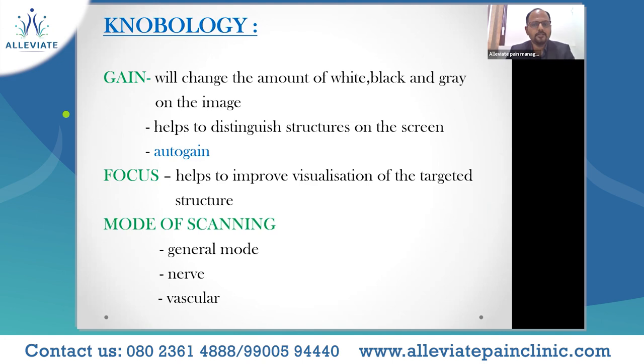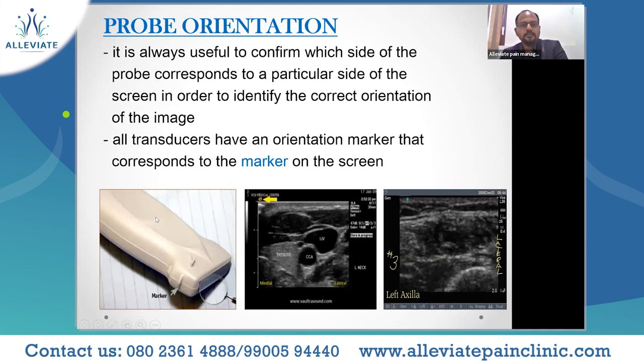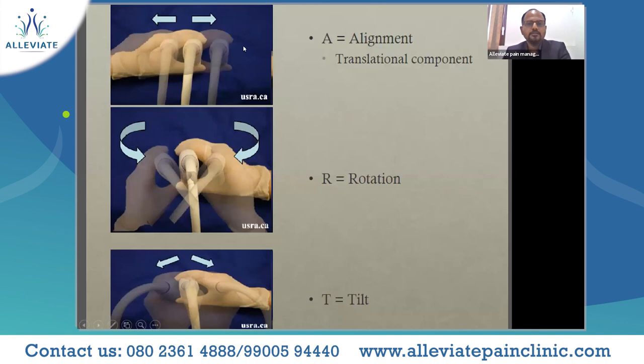Coming to the last part — knobology. Gain changes the amount of white, black, and gray on the image, helping to distinguish structures on the screen. Focus helps to improve visualization of the target structure. Important: the mode of scanning — whether general mode, nerve mode, or vascular mode. Depth settings to see deeper structures; ideally depth should be set about one centimeter deeper than the target of interest. Probe orientation: the marker on the screen tells us which side of the image we are visualizing. Probe manipulation uses the mnemonic PART: P for pressure, A for alignment, R for rotation, and T for tilt.